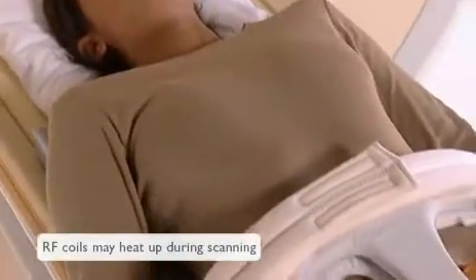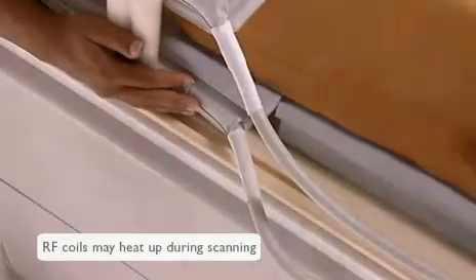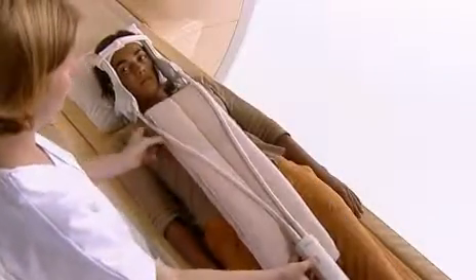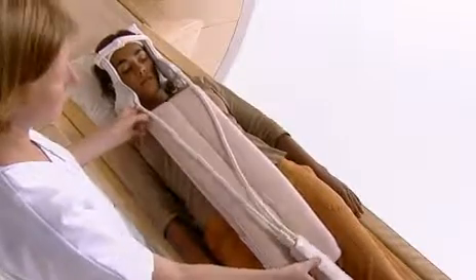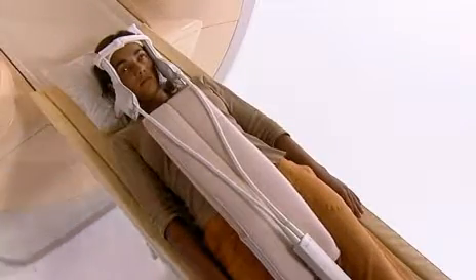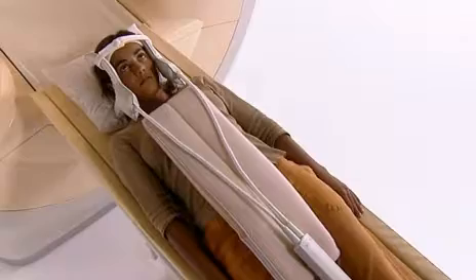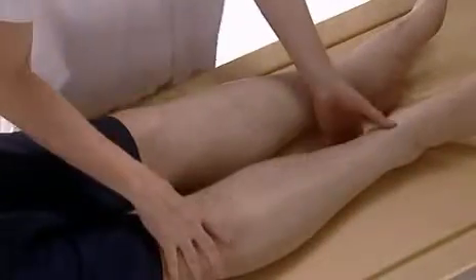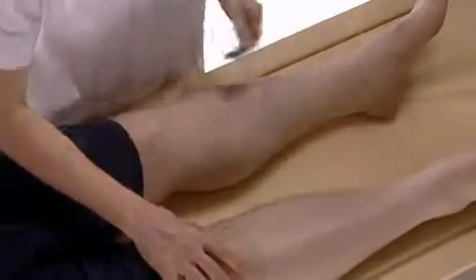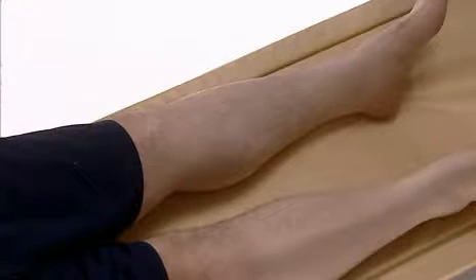A cable or component in contact with the patient's skin can heat up and cause a burn. Currents running below the skin can cause internal burns. In this case, the component is not heated. In the case of skin-to-skin contact, the surface area is small so that high energy discharges can occur.